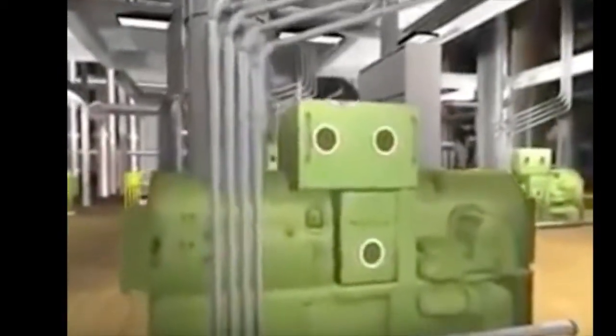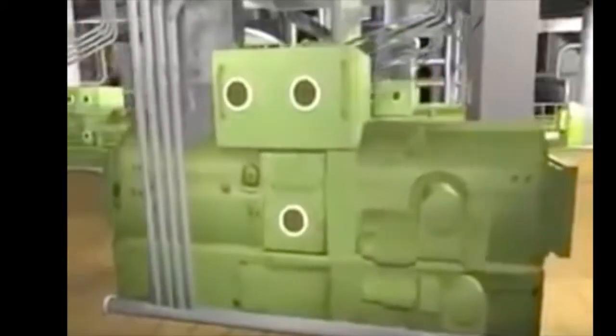So now the coal is transported back into the plant, where storing and pulverizing takes place. Once the coal is inside the plant, up to a 30-hour supply of coal can be stored in bunkers. The coal moves from the bunkers to feeders to be measured and moved to pulverizers. Each generating unit has 16 coal feeders that supply 8 pulverizers. Coal enters the pulverizers and spins in these large drums, where hundreds of steel balls grind it into a fine powder. Now this fine powder leaves the pulverizers and heads to the boilers.